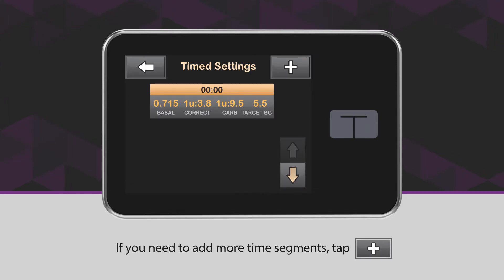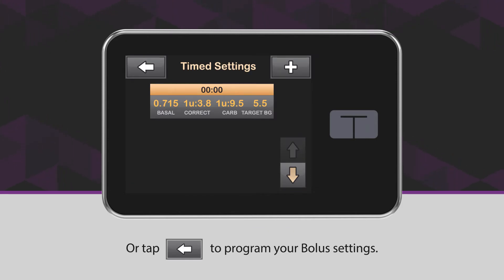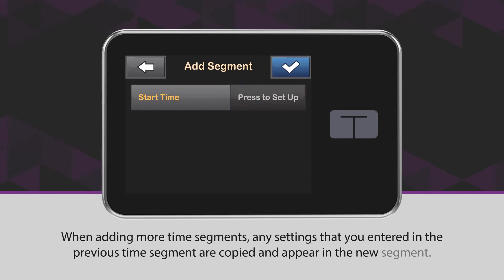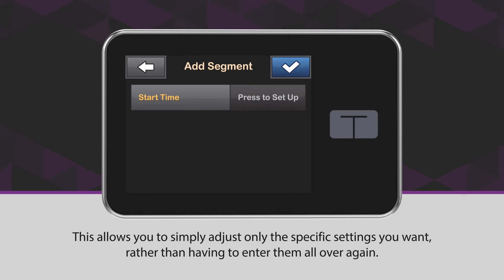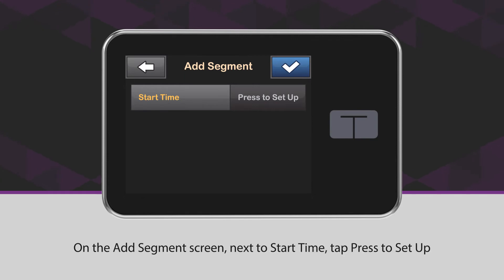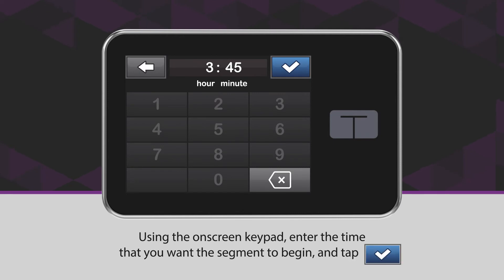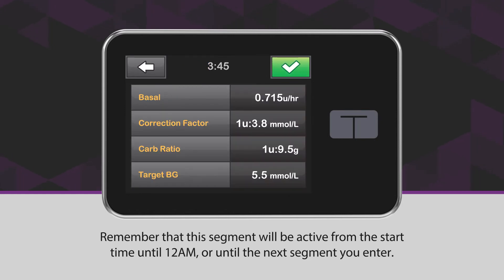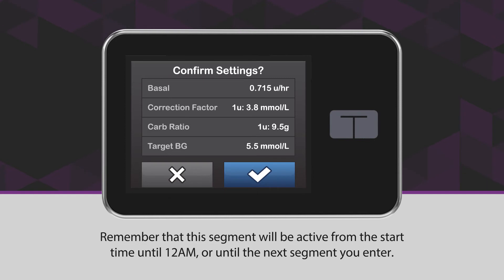If you need to add more time segments, tap the plus icon, or tap the back arrow icon to program your bolus settings. When adding more time segments, any settings that you entered in the previous time segment are copied and appear in the new segment. This allows you to simply adjust only the specific settings you want rather than having to enter them all over again. On the Add Segment screen, next to Start Time, tap Press to Set Up. Using the on-screen keypad, enter the time that you want the segment to begin and tap the blue checkmark icon. Remember that this segment will be active from the start time until 12 AM or until the next segment you enter.